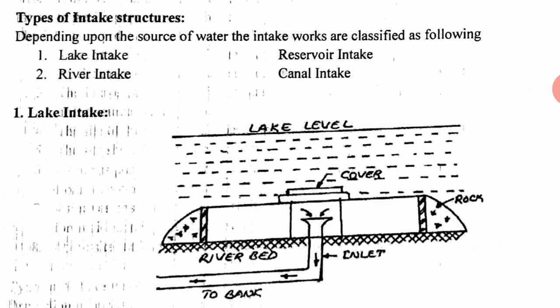Intakes are structures which essentially consist of an opening, grating or strainer through which the raw water from river, canal or reservoir enters and is carried to the sump well. By means of conduits, water from the sump well is pumped through the rising mains to the treatment plant.